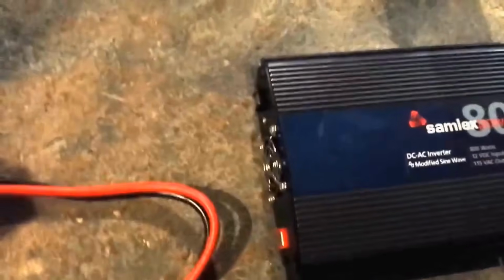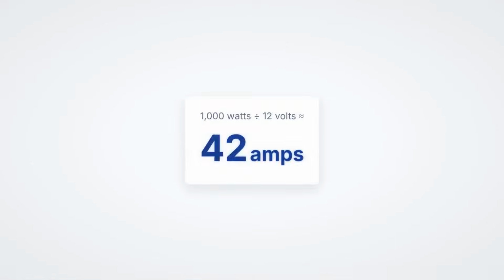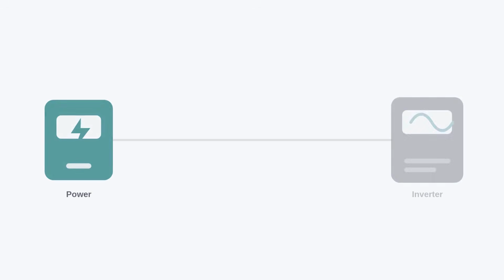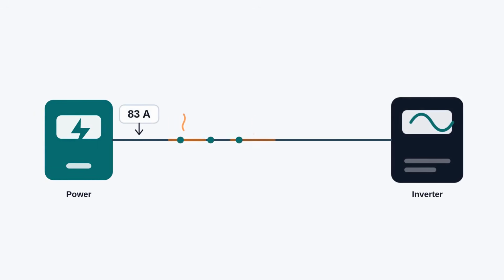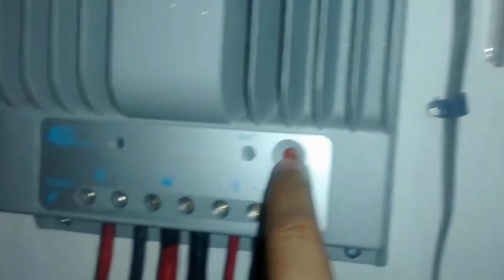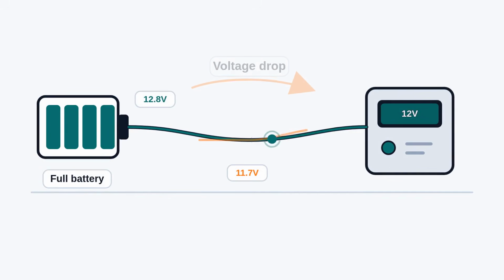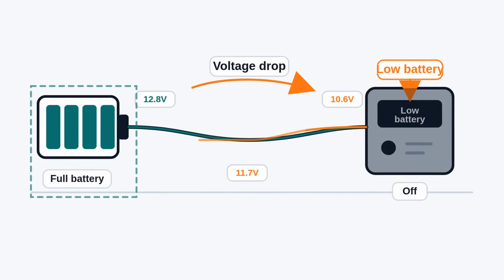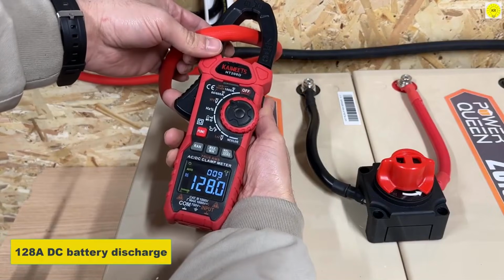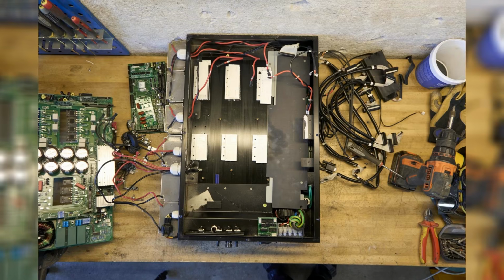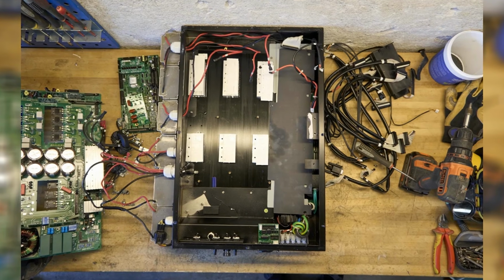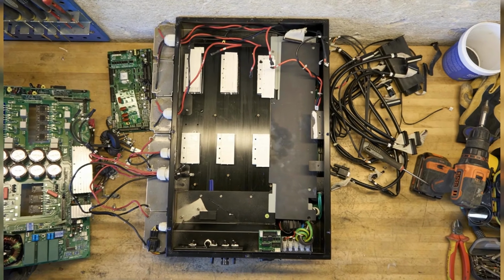At 12 volts, current runs high. A 1000-watt inverter at full load pulls roughly 83 amps. Push 83 amps through undersized cable, and resistance does not just waste energy, it drops voltage. The inverter does not measure battery state of charge, it measures terminal voltage. Drop enough voltage across a thin cable, and the inverter reads a weak battery and shuts down, even if the battery itself still holds a usable charge. That is a nuisance shutdown caused entirely by wire, not by a depleted system.